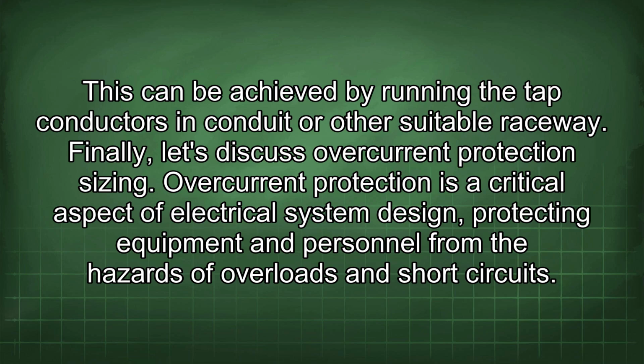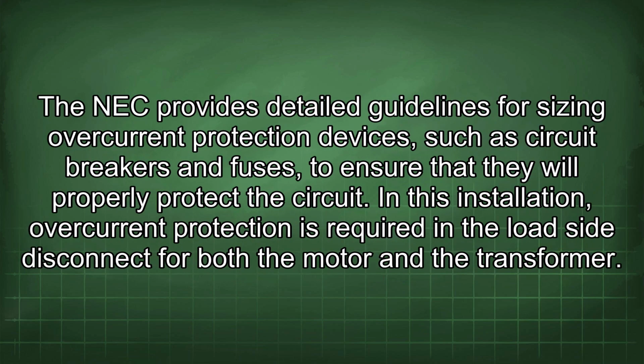Finally, let's discuss overcurrent protection sizing. Overcurrent protection is a critical aspect of electrical system design, protecting equipment and personnel from the hazards of overloads and short circuits. The NEC provides detailed guidelines for sizing overcurrent protection devices, such as circuit breakers and fuses, to ensure that they will properly protect the circuit. In this installation, overcurrent protection is required in the load side disconnect for both the motor and the transformer.